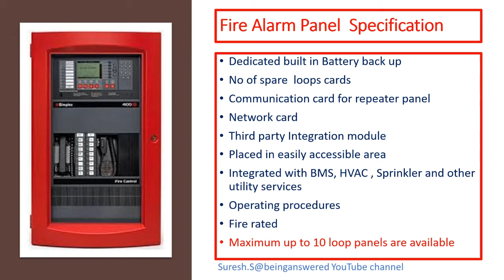Communication card to be considered for repeater panel extension. Network card to be considered for networking integration. It should be feasible for third-party integration. This panel should be placed in an easily accessible area so that in case of any emergency, people can access the panel easily. Operating procedure should be understood clearly by the facility team so that in case of emergency, it will be easy to handle the situation. This panel should be kept in a fire rated enclosed room.